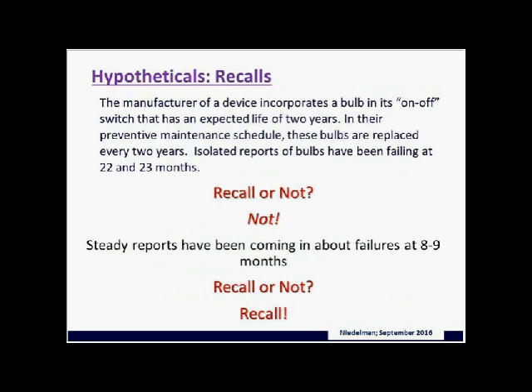So here's a hypothetical. Again, the manufacturer's device incorporates a bulb and its on-off switch that has an expected life of 2 years. In their preventive maintenance schedule, these bulbs are replaced every 2 years. Isolated reports of bulbs failing at 22 and 23 months. Is that a recall or not? I would say no. That's pretty close to the expected life, and they're isolated reports.